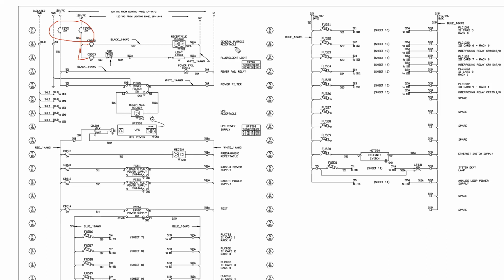This one I know is for a programming laptop. So this is going to be mounted somewhere where you can plug a laptop into. It's not going to be for a power drill or a heat gun for doing shrinking wire labels. This is for allowing an integrator or somebody in the panel to power up their laptop. Here you've got another circuit breaker, goes down to 2 amps. There's a door switch, and then there's a light. So this door switch is mounted in the panel in such a location that when the door is open, the light is going to be closed, or the light is going to be on rather.